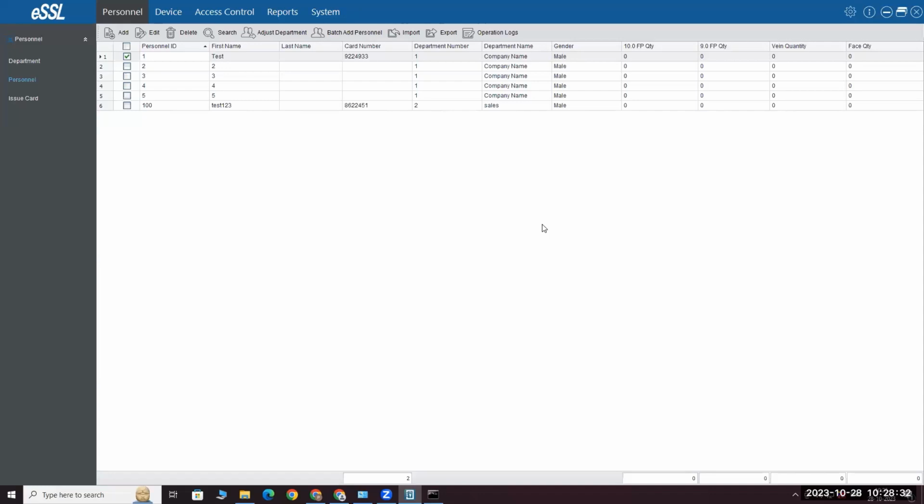I already mentioned that. You can take a biometric device which has a Wiegand out and connect it with that controller. On the controller side, we have Wiegand ports for a Wiegand connection. Normally we connect KR500 readers there; in that place you can connect biometric devices. In this C3200 you can connect 4 readers, 2 readers for a single door. So if you want to use 2 biometric devices for 1 door, you can use them as entry and exit in the C3200.